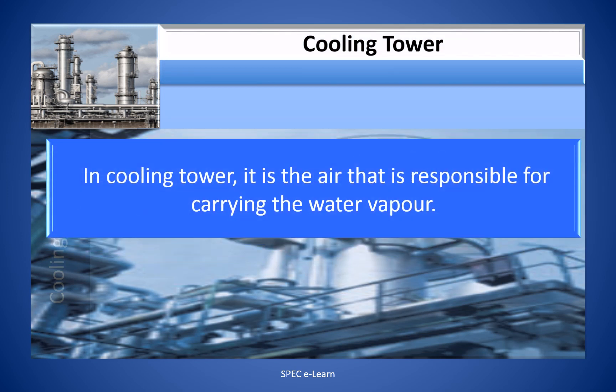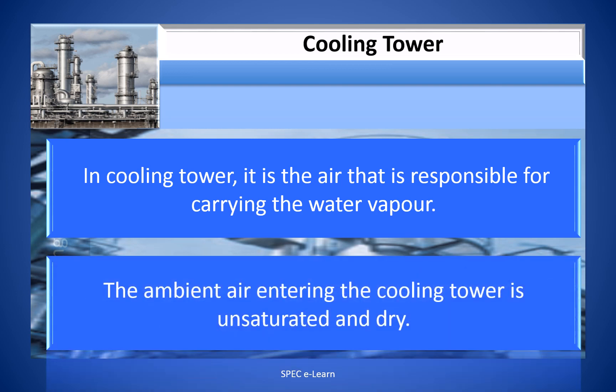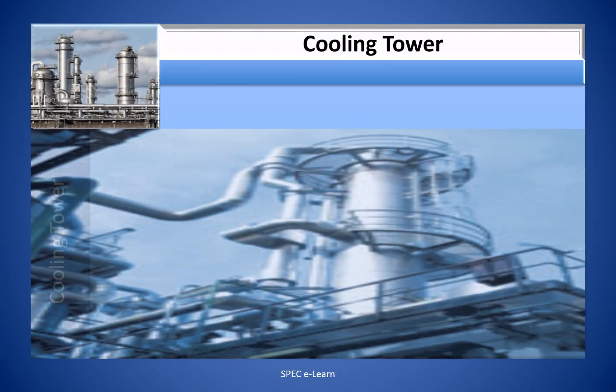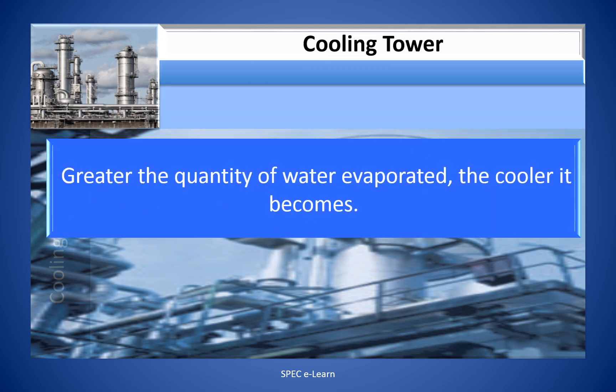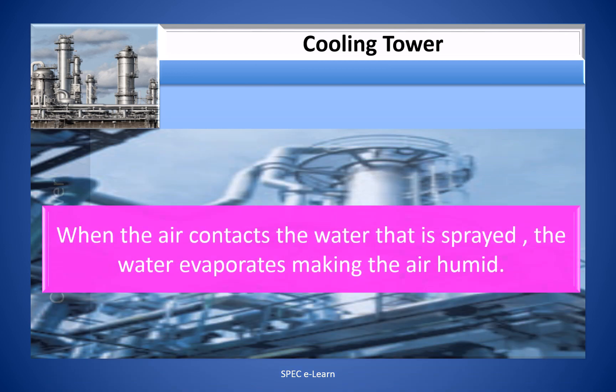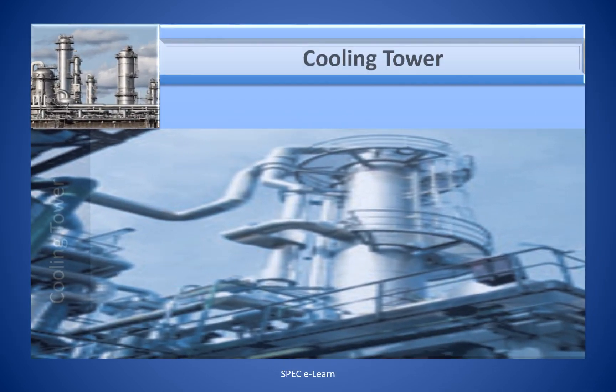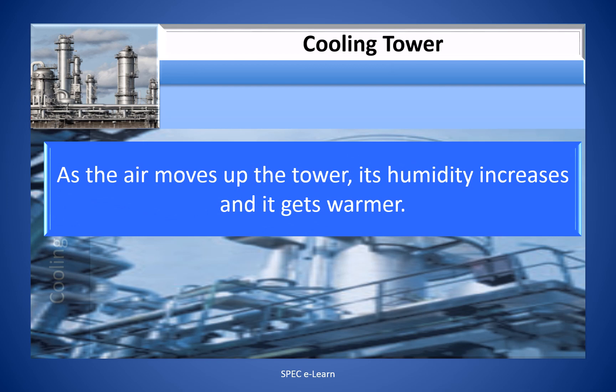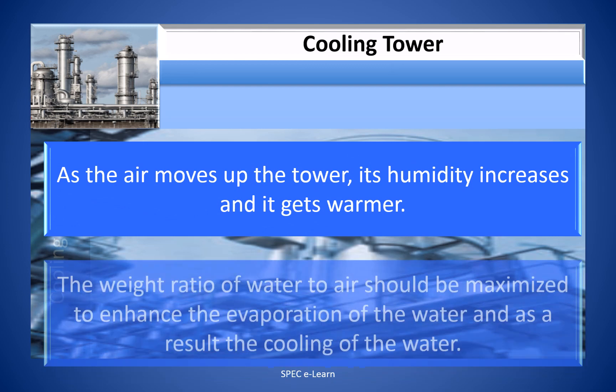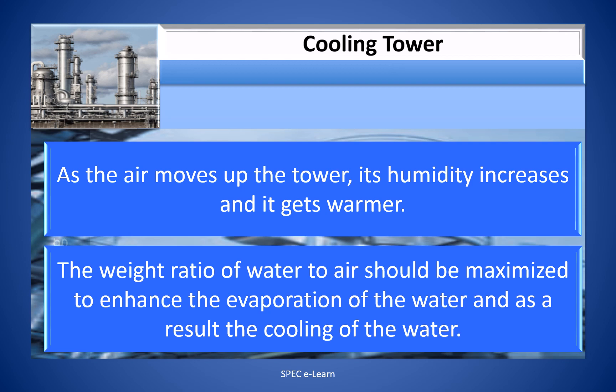In the cooling tower, it is air that is responsible for carrying the water vapor. The ambient air entering is unsaturated and dry. The greater the quantity of water evaporated, the cooler it becomes. To accomplish this, the flow of air — which carries away the vapor — should be increased. When air contacts the sprayed water, the water evaporates, making the air humid. As the air moves up the tower, its humidity increases and it gets warmer. The water-to-air mass ratio should be maximized to enhance cooling.